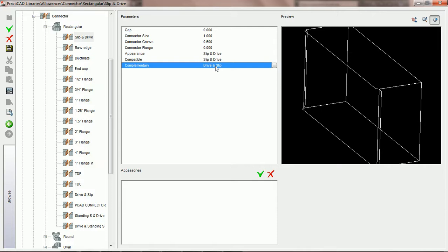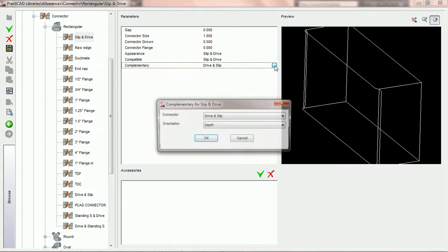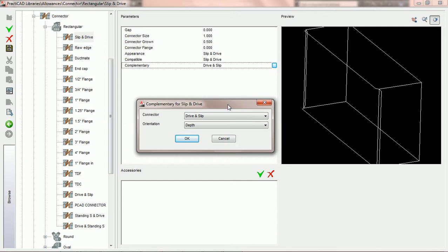Now currently in this tutorial, it's already set to do so, but to show you how you would set it to what you'd like, you'd come over here to the dialog box, click on it, and then answer the two questions in the complementary field. The first one is, what connector should be complementary with slip and drive? In this particular case, we've said drive and slip. That means that if we were to take two pieces of duct and rotate the second piece of duct 90 degrees, then instead of using the compatible connector, it should switch and use the complementary connector.